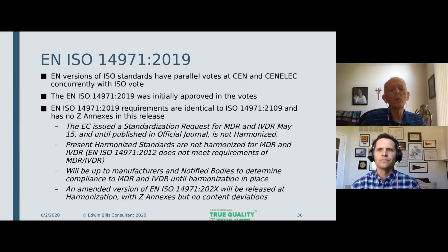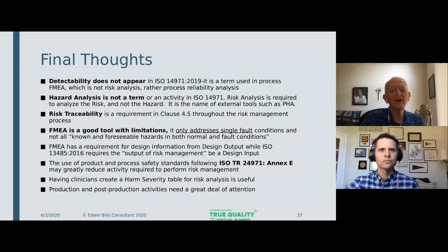With the completion of the standardization request, CEN and CENELEC will issue an amendment to 14971, which will be published as a 2020 edition, hopefully, and it'll be released with Z annexes, but they will have no content deviations. They will only have the tables that compare the standard with the regulation. Final thoughts. Detectability does not appear in 14971. The term used in process FMEA, it's not risk analysis. So that term has no place in 14971.